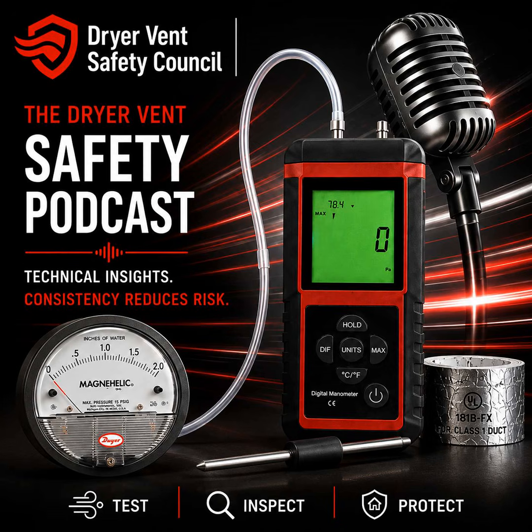No, it is absolutely not a standard. It's not the exclusive, it's not the preferred, and it's not the definitive way to test a dryer. I want to be incredibly clear on this point. Go ahead. This is another tool available to technicians for evaluating dryer exhaust performance. Okay, so it's an option. Exactly. Rather than replacing airflow or back pressure testing, this method provides an additional way to evaluate system performance by measuring negative pressure inside the dryer.